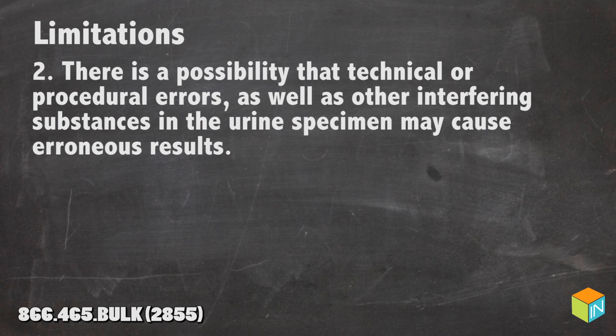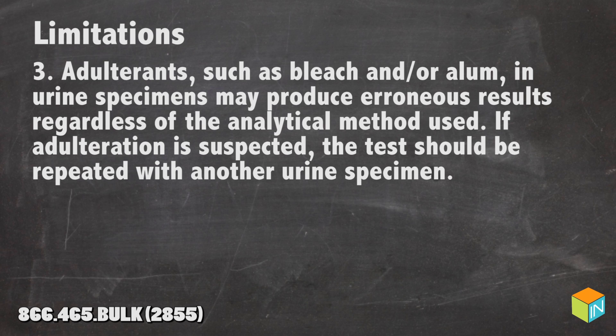Limitation 2: There is a possibility that technical or procedural errors, as well as other interfering substances in the urine specimen, may cause erroneous results. Adulterants such as bleach or alum in urine specimens may produce erroneous results regardless of analytical method used. If adulteration is suspected, the test should be repeated with another urine specimen.